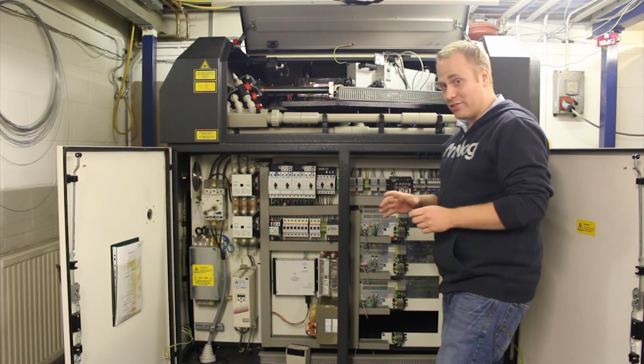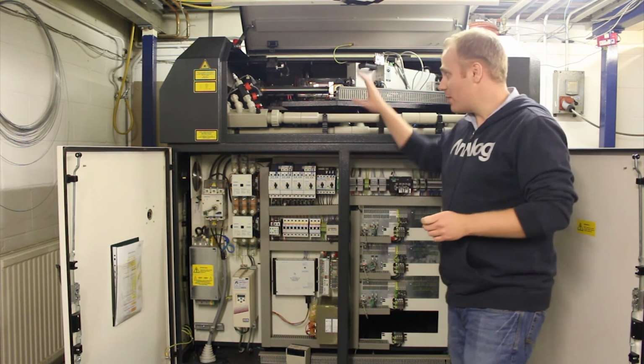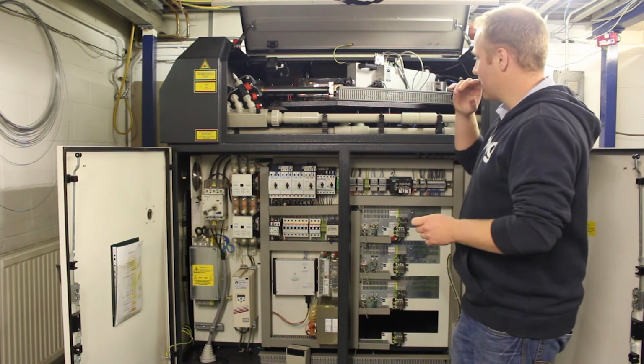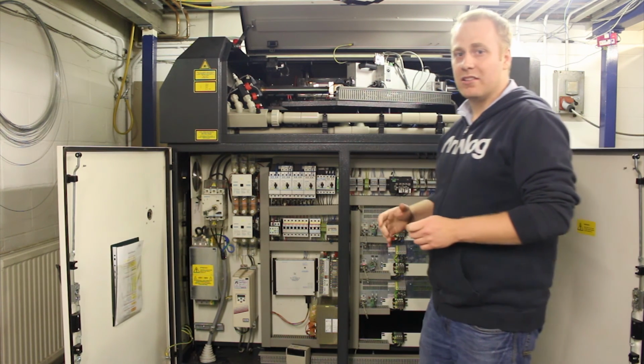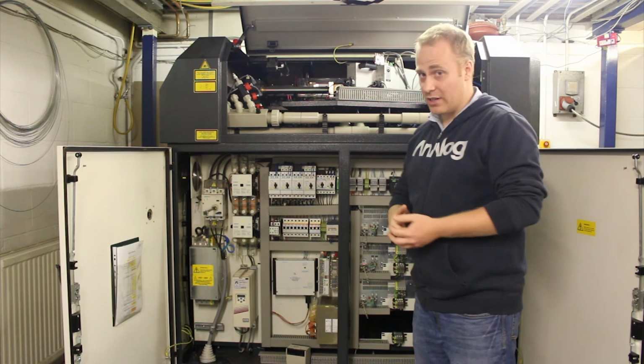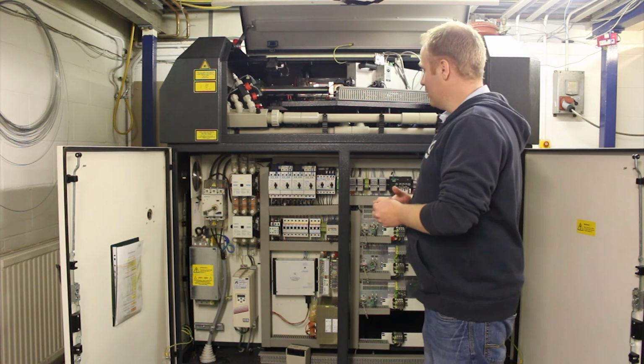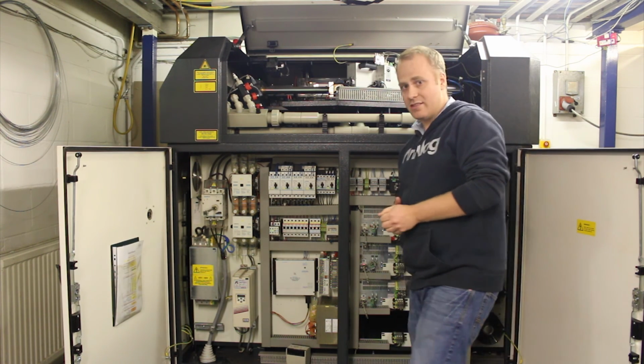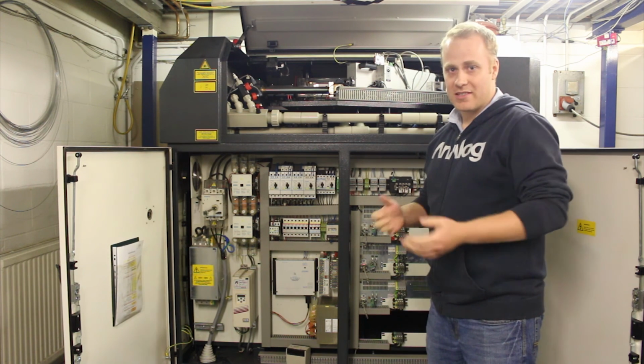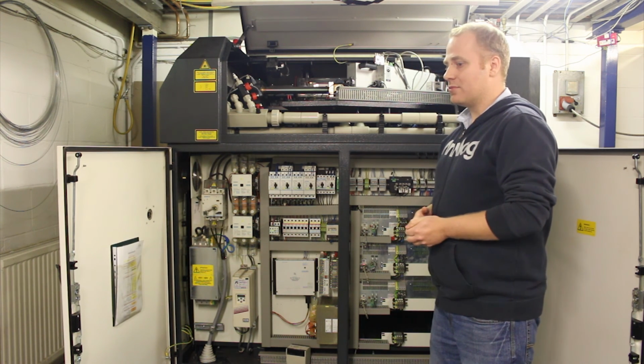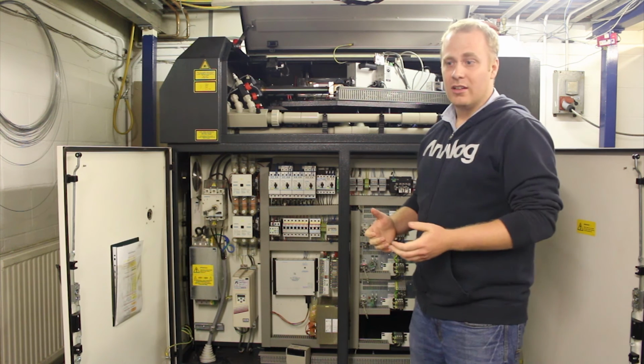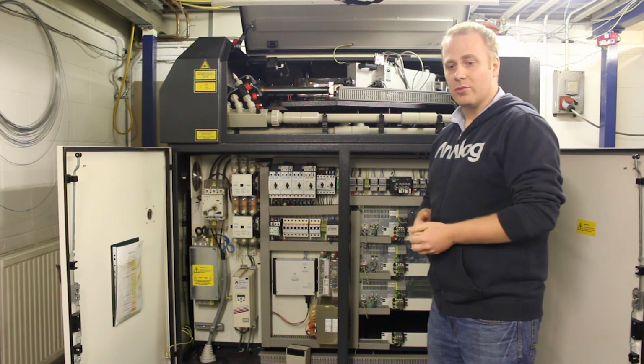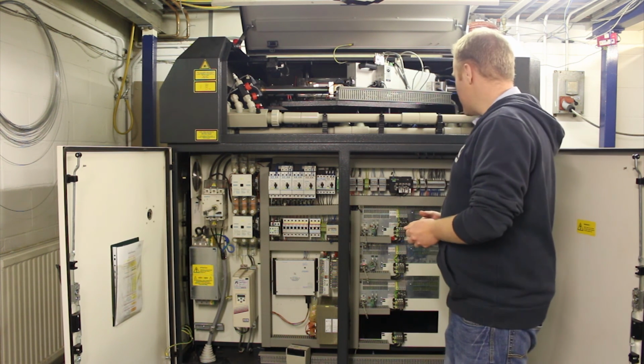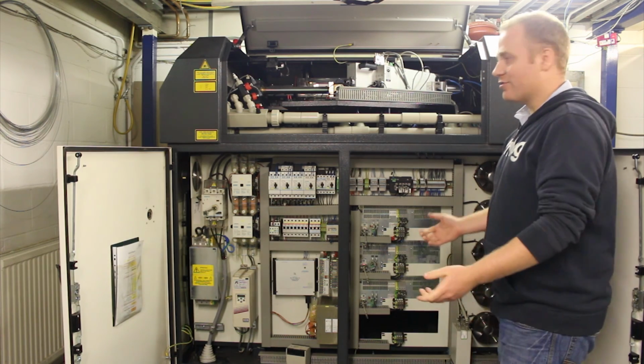They've gone to a lot of effort to put humidity sensors inside the pump chambers up on the optics deck, and those seem to be reading high humidity within the pump chambers. So we need to determine what that means, see about getting them desiccated, and if it's a problem, we need to solve it. We're going to do some looking into that. So yeah, that is an overview of the front of Stan.